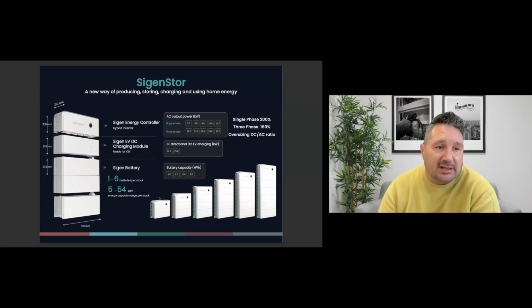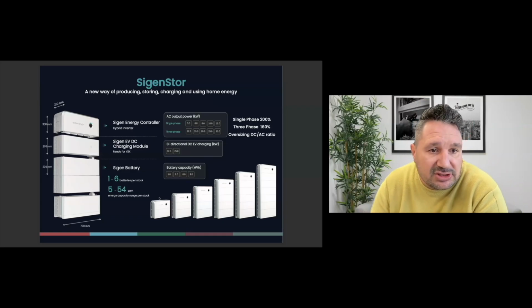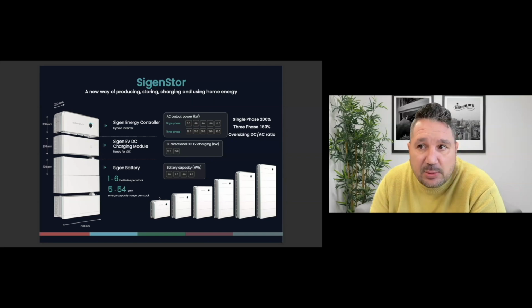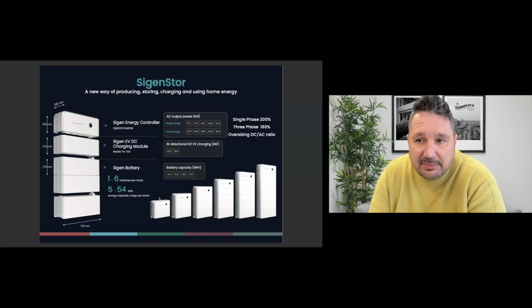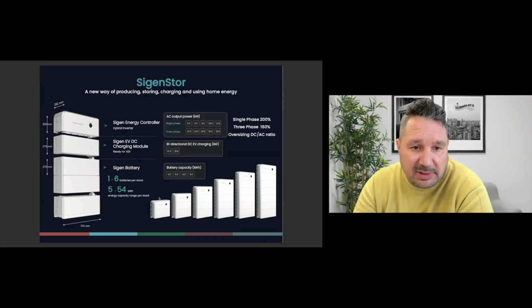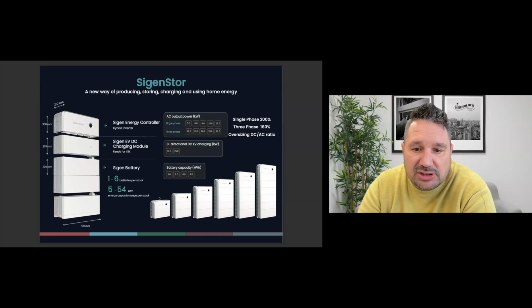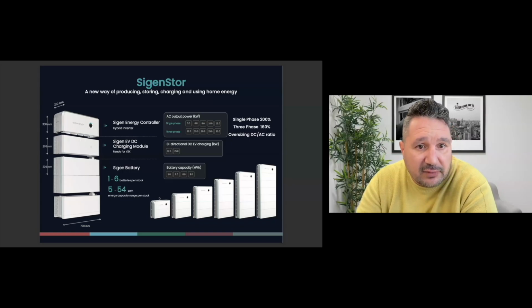The energy controller is sitting at the top, measures a size of 300 by 260, and that is whether it is a 5 kilowatt single phase all the way up to 30 kilowatt three-phase inverter. The inverter stays exactly the same. These can also be overpaneled by 200% on the single phase units and 160% on the three-phase systems. It's a full DC optimized system, which means you can charge the batteries as well as supply the load, and the inverter size is not limiting the energy throughput on the DC side.